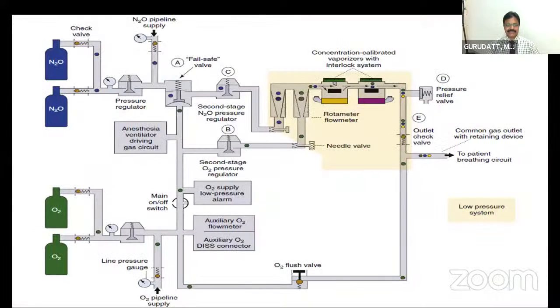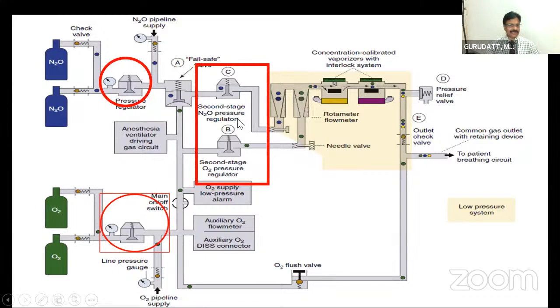Now, you have 2 kinds of pressure regulator. One is the primary or first stage pressure regulator. These first stage or primary pressure regulators are present downstream of the yoke assembly, just between the yoke assembly and the flow control or flow meter assembly in most of the anesthesia machines and in the workstations. Just before the fail-safe valves, the primary or first stage pressure regulators are there. In the case of GE machines, we do have second stage pressure regulators also. These second stage pressure regulators in GE machines are just upstream of the flow control or flow meter assembly. So let us discuss these primary pressure regulators.